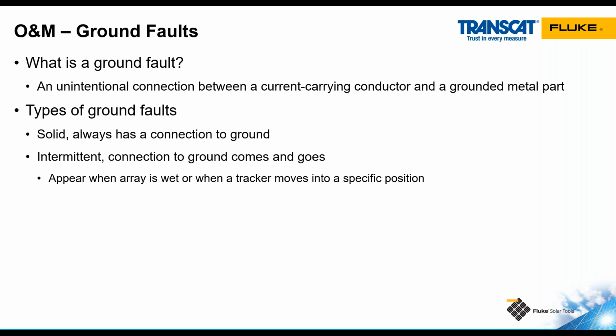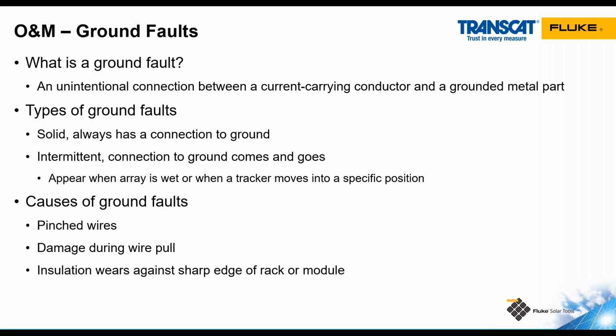Intermittent ground faults, on the other hand, have a higher resistance connection, and they tend to come and go. We may see them when the conditions on site are wet, or, for example, when a tracker moves into a certain position, it may pinch the wire and cause the ground fault. Many different things can cause ground faults: pinched wires, like in the tracker system I just described, or sometimes the wire gets pinched between the module frame and the racking during installation. Wiring can be damaged when it's being installed, or maybe the wire was improperly managed and it's rubbing against a metal part, and eventually that insulation wears away, and now I've got an intermittent ground fault usually at first, and then it becomes a solid ground fault over time.